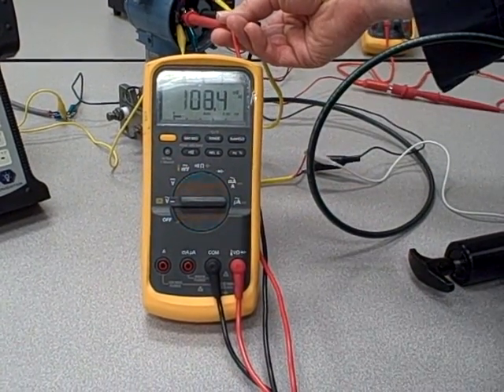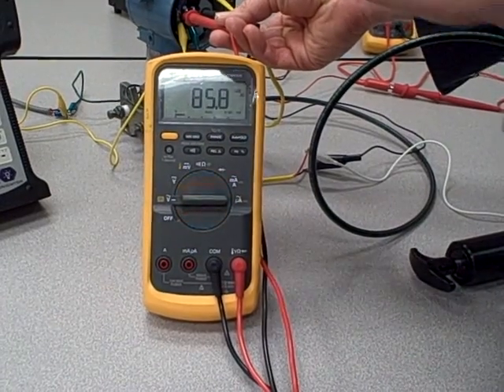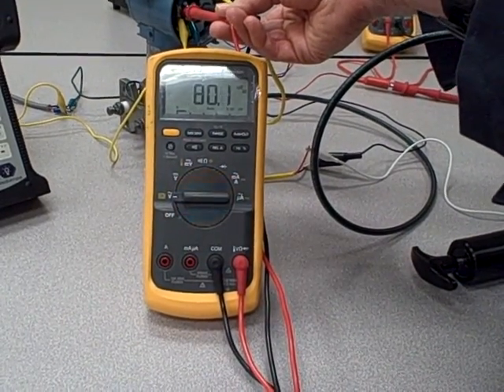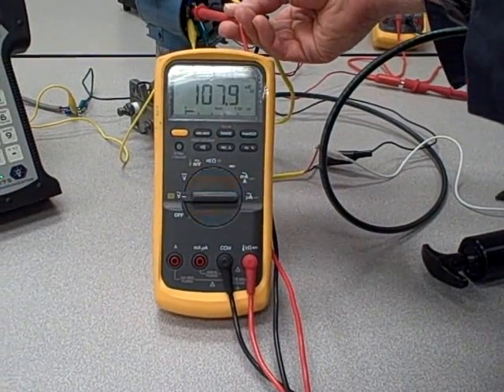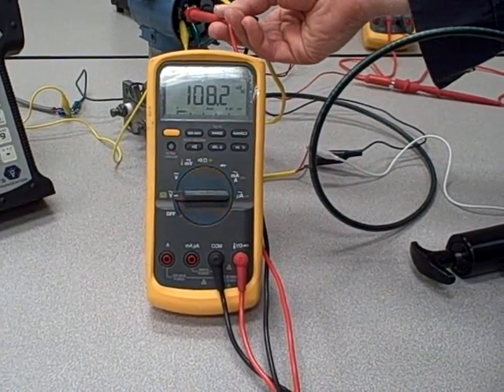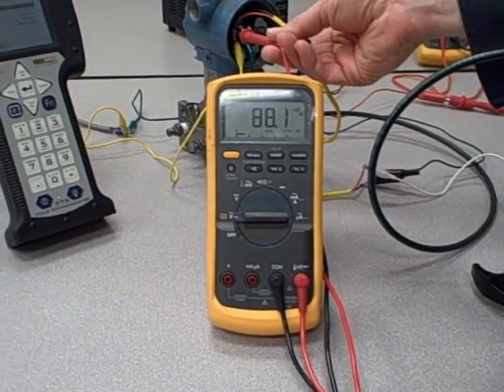That signal you see right there, the 100 millivolts or so AC voltage, is what is constituting the digital signals between the field communicator and the transmitter, talking back and forth. Those pulses of voltage, binary ones and zeros, communicating digital information.